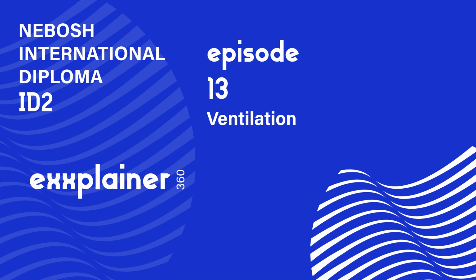Good old-fashioned smoke. Using smoke tubes, pellets, or generators to create artificial smoke. And you just watch where the smoke goes. Yep. You release it near the point of contaminant generation and watch. Does it get drawn smoothly into the hood? Does it define the capture zone clearly? Or does it just swirl around and drift away? It's a very direct way to assess if the hood is actually capturing effectively, especially for larger systems.